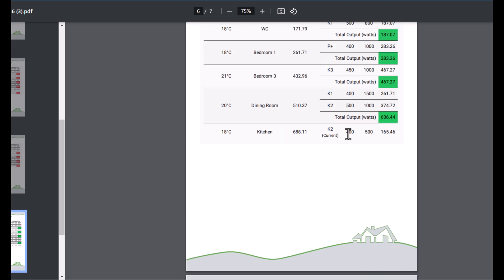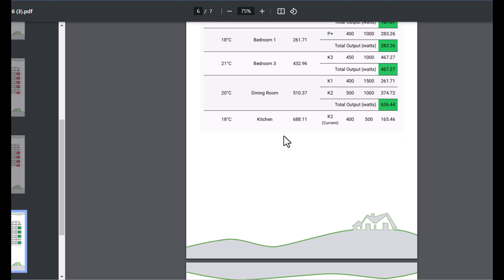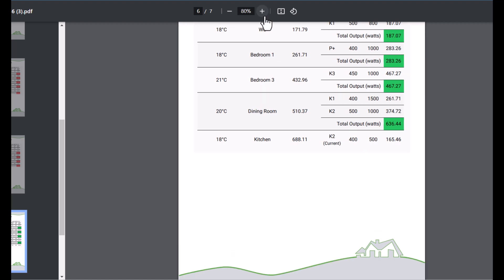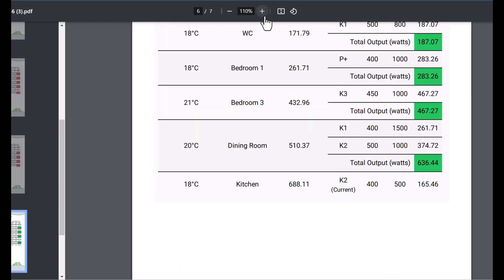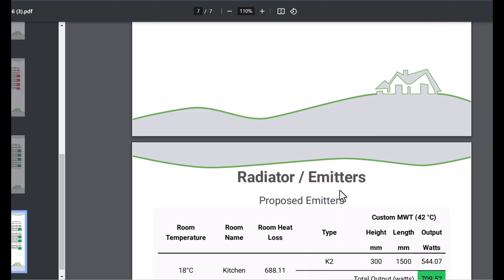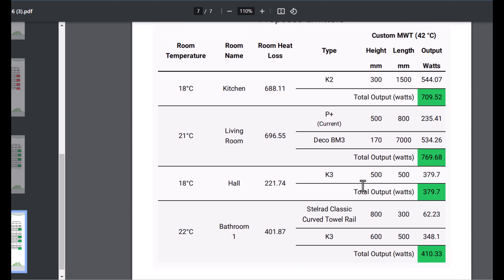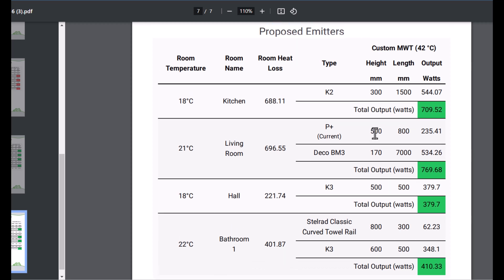Now we know that these particular radiators are actually going to meet the demand for the lower flow temperature from this air source heat pump. I can see in fact for the kitchen here we're leaving 1K2 in there. If I just zoom in a minute, you can see currently we've got that radiator in there.